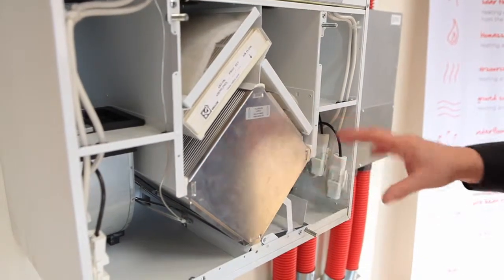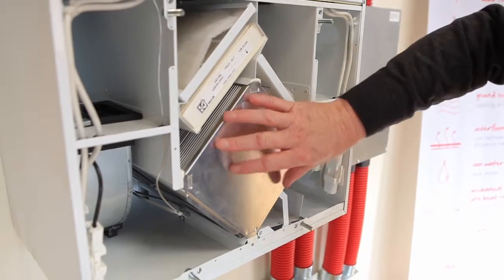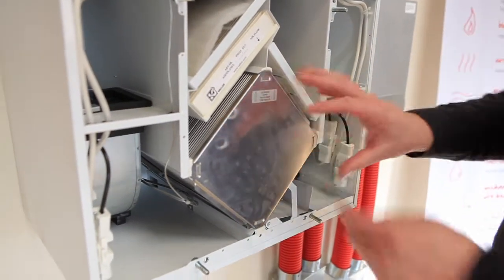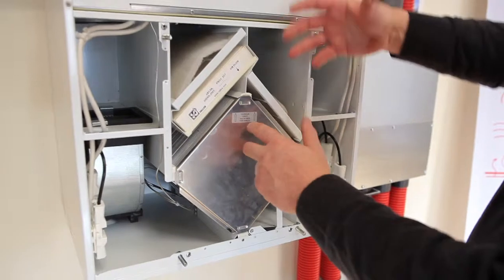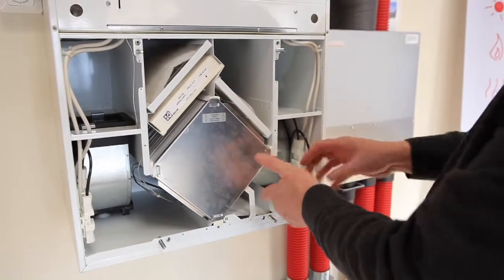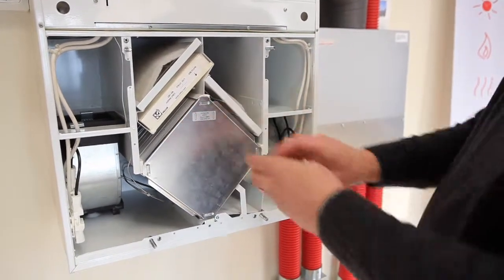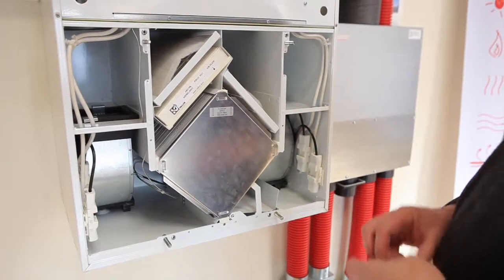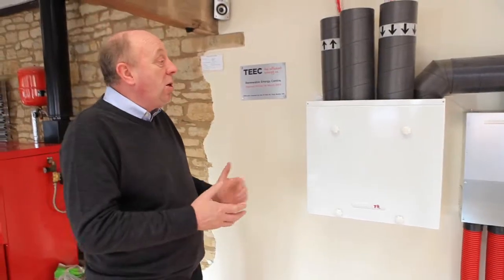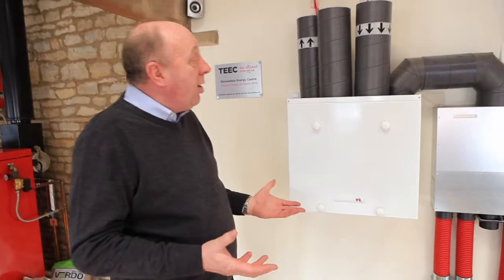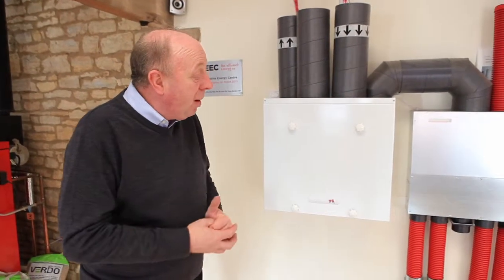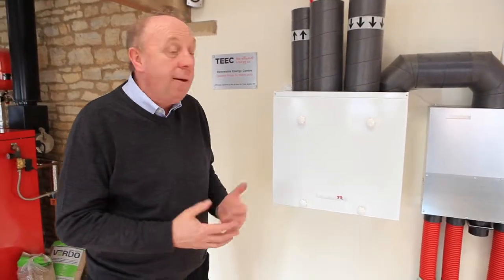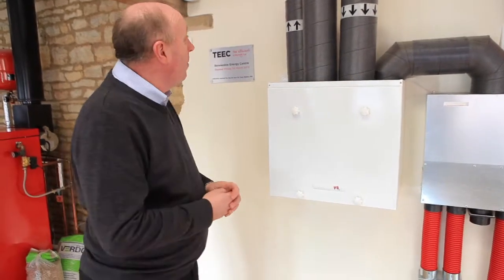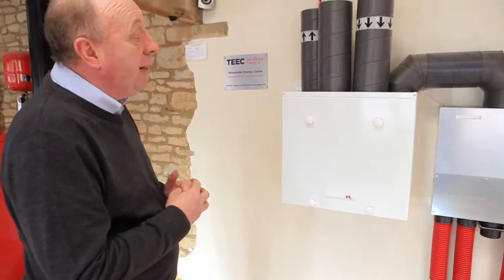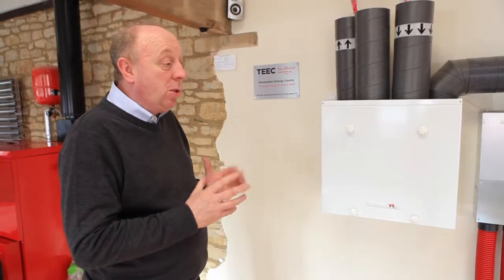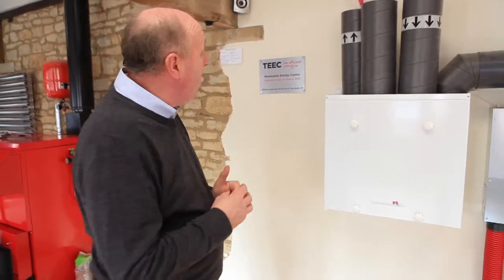We can see the channels, how the extract air comes through. It circulates around this heat exchanger, which gathers the heat. Fresh air is coming in over that heat exchanger and delivering that latent and waste heat back into the property. So we have a solution there for extraction from the property, and we replace the air in the winter with warm air, and in the summer we can cool it. That is how a mechanical ventilation heat recovery will deal with that in a well-insulated building.